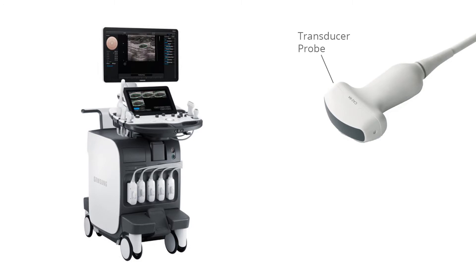Transducer probe. The transducer probe both transmits and receives the ultrasound waves using the effect of piezoelectricity. Inside the probe, there are one or more piezoelectric crystals. When electrical pulses are applied to the crystals, they oscillate and produce ultrasound waves. There is a sound-absorbing backer layer behind the crystals to eliminate back reflections, and an acoustic lens in front of the crystals to focus the emitted waves.